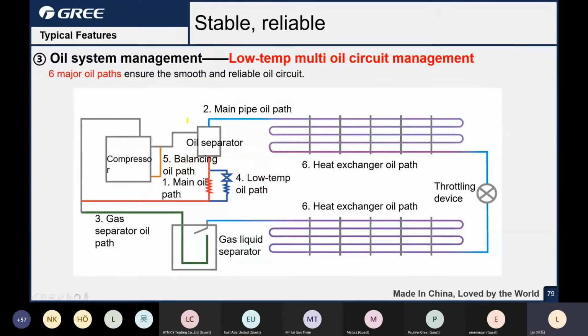Another one is the oil return system. There are 6 major oil paths. First one is the oil return from the oil separator, the red line, the oil return. That's the main oil return. Another one is the low temperature oil return. You can see there is a lot of oil return pipe. If the ambient is very cold, this oil return solenoid valve and capillary will open to get more oil from the oil separator. And in the discharge and suction, there is an oil balancing path here, the number 5 oil balancing. That's a lot of oil path.